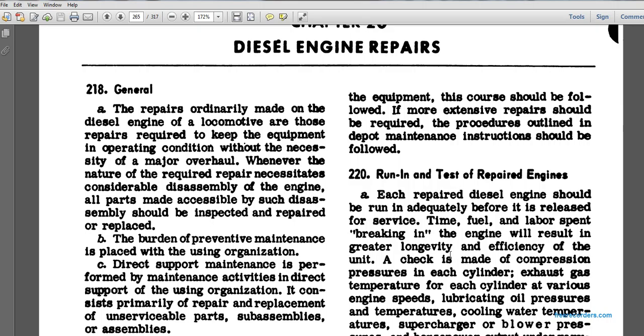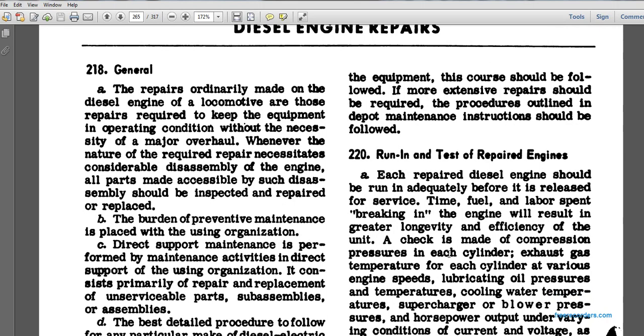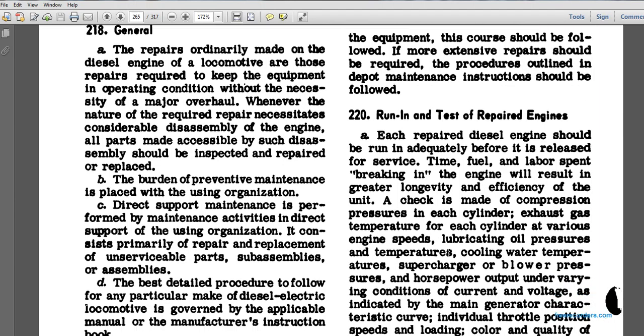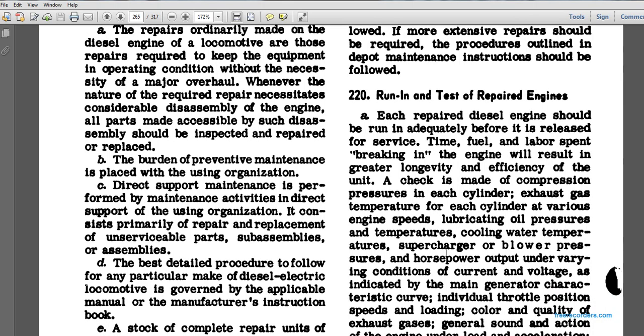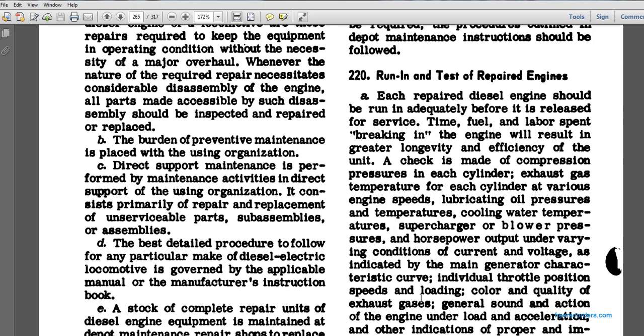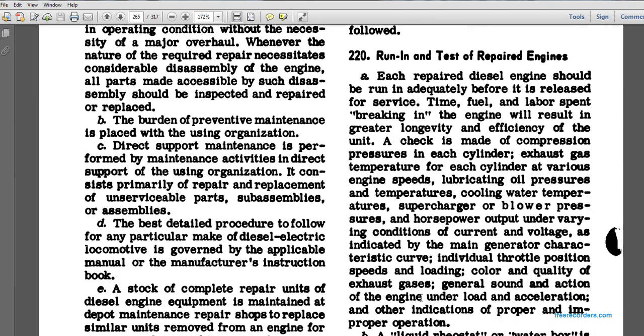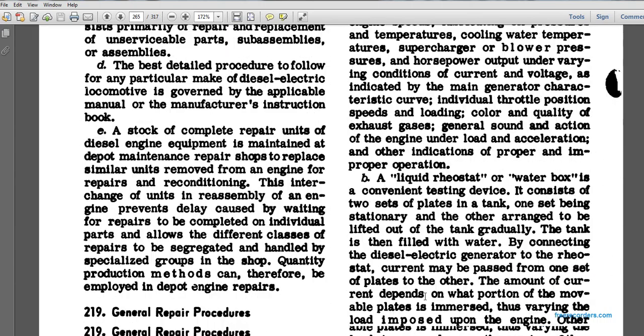A check is made of the compression in each cylinder, the exhaust gas, and the temperature of each cylinder at various engine speeds, lubrication, oil temperatures, cooling water temperature, supercharger blower pressure, and horsepower output under varying conditions, over the current and voltage as indicated by the main generator characteristics curve. The individual throttle position, speed and loading, color and quality of exhaust gases, general sound, action of the engine under load, acceleration, and other indications of proper and improper operation are observed.